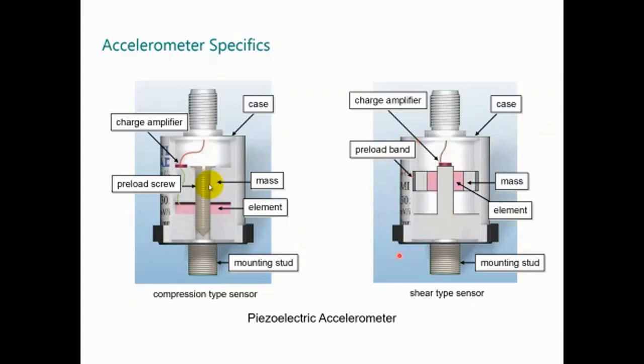What is the advantage of the shear type? The shear type is less susceptible to effects of high temperature, because high temperature dilates the casing. And when we dilate the casing, it changes the preload force. The shear type is less susceptible to temperature or any deformation in the case. Both have the sensitive axis.